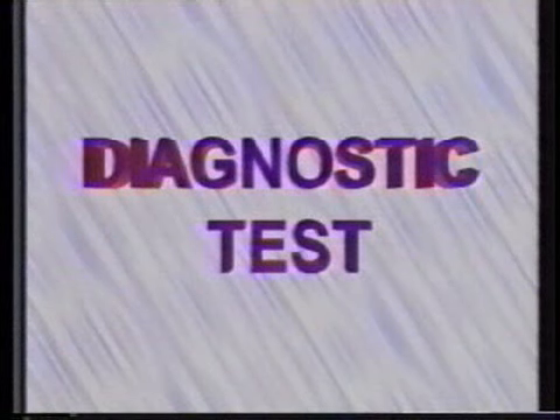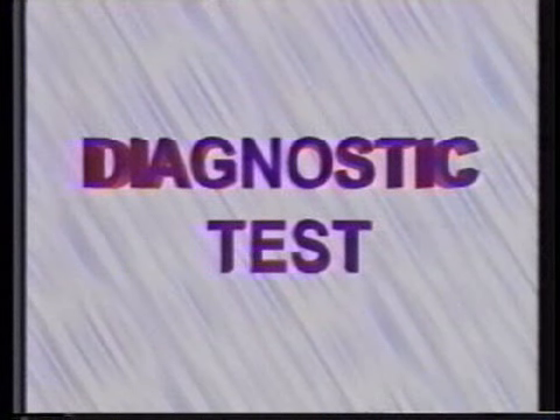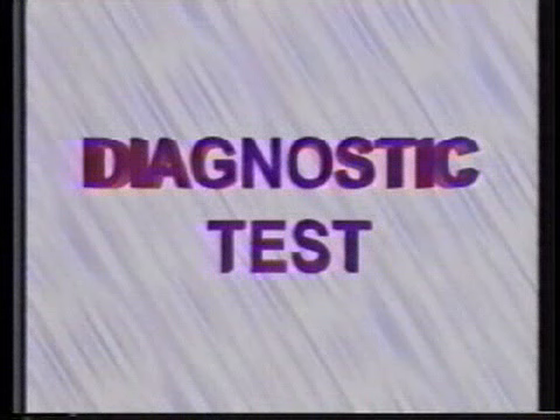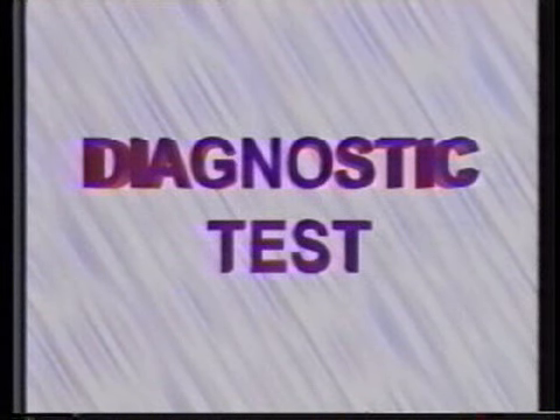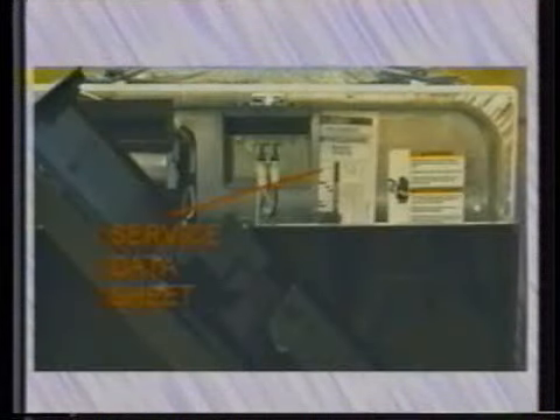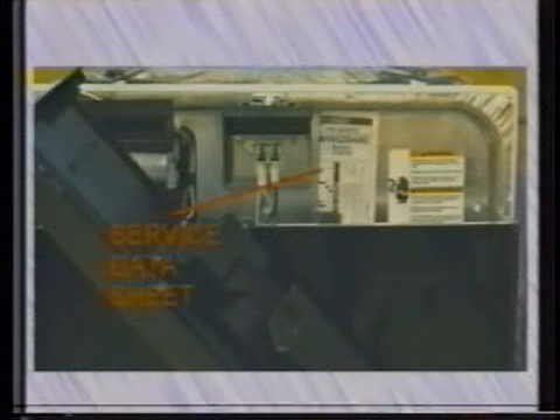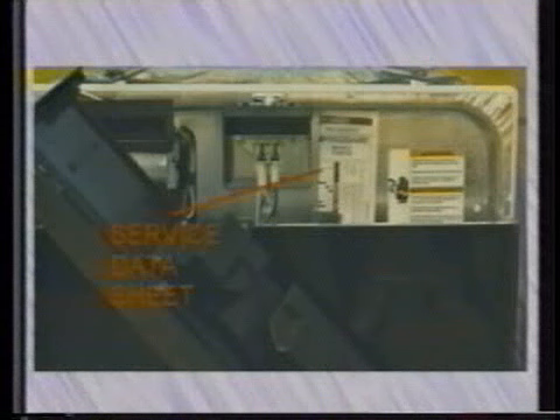The other thing we need to talk about before going into troubleshooting is called the diagnostic test, and this allows us to rapidly advance the electronic control through the cycle so that we can test each component. The service data sheet contains information on how to start the diagnostic test and also gives you a matrix on when each component is going to be operated.